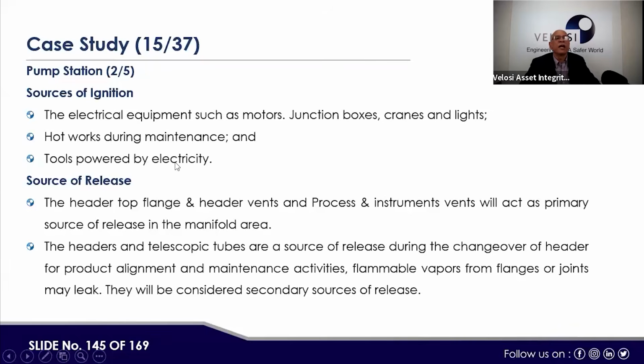Source of ignition: electrical equipment such as motors, junction boxes, cranes, and lights, hot work during maintenance, and tools powered by electricity. Source of release: the header, top flange, header vent, and process instrument vents will act as a primary source of release in the manifold area. The headers and telescopic tubes are a source of release during the changeover of the header for product alignment and maintenance activities. Flammable vapors from flanges or joints may leak, and these will be considered a secondary source of release.